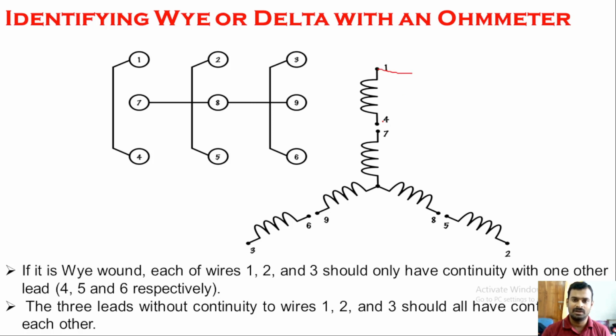So we know what we mean by continuity test. Simply by measuring the resistance between the coils, you can come to know whether there is continuity or not. So we should have a table and verify whether the table is satisfied, whether it is satisfying the delta configuration or the star configuration. If you connect the multimeter across this coil, the resistance will have a small value, either 4 ohms or 5 ohms based on the motor. Different types of motors may have different values as well. And if you connect the same first terminal with the seventh terminal with the same ohm meter, what is going to happen? It is going to show infinite resistance.